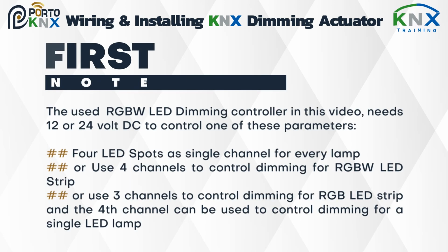The RGBW LED dimming controller used in this video needs 12 or 24 volt DC. It can control LED spots as a single channel for every lamp, or use 4 channels to control dimming for an RGBW LED strip, or use 3 channels to control dimming for an RGB LED strip, and the 4th channel can be used to control dimming for a single LED lamp. All of these functions can be selected in the ETS program.